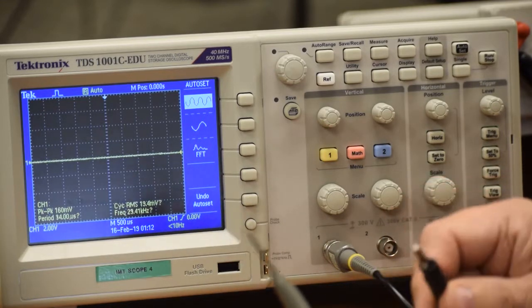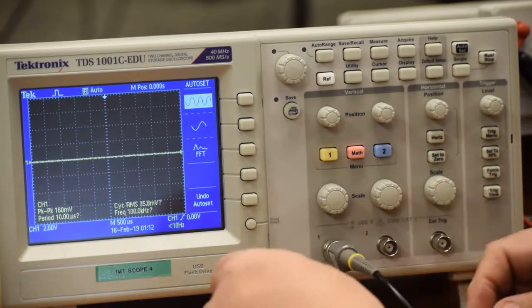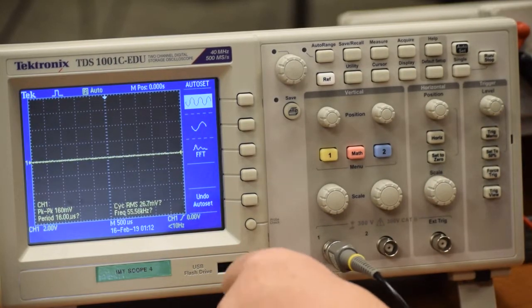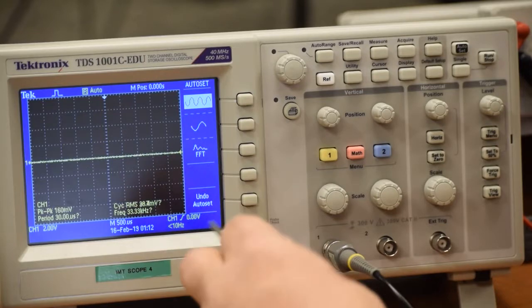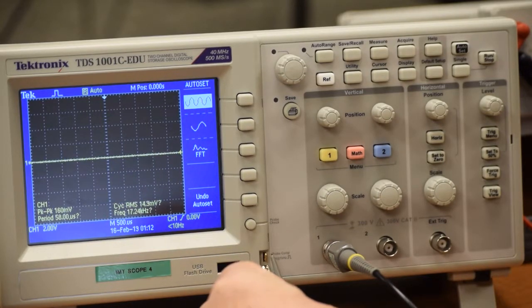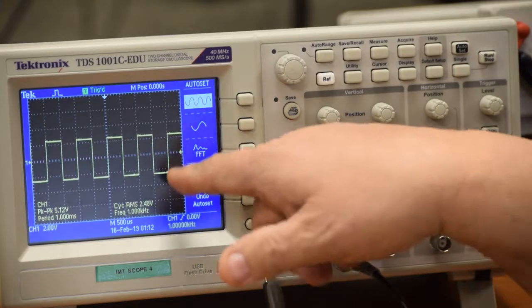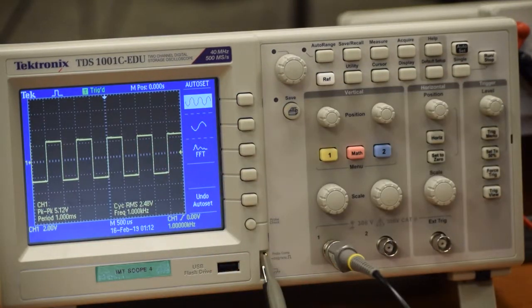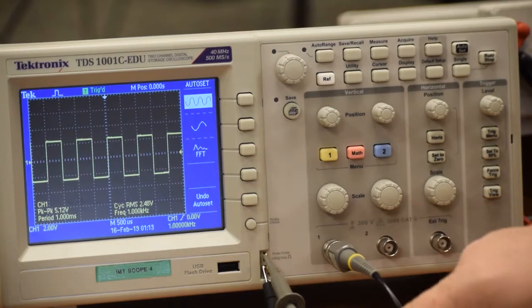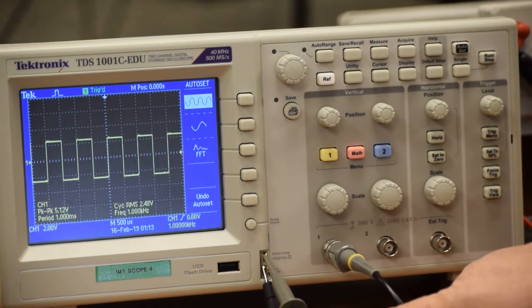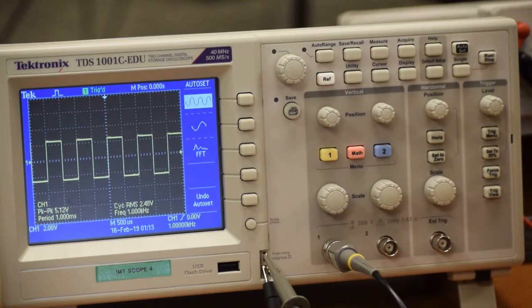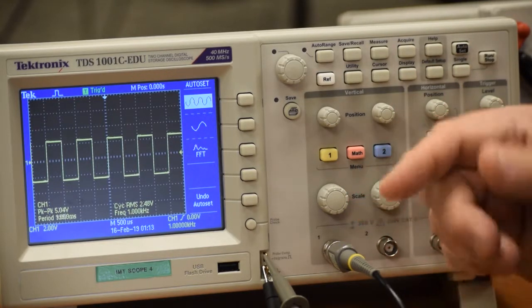And one of the first things you want to do, and you have a capability here where it's already permanently installed as a ground connector, and then you put your OScope on this point right here. Notice we just went to a square wave. And that's how you would make adjustments and calibrating the probe. It's a good idea to do that daily. You want to be on times 10, and I'll talk about that in a moment, but the probe should be on times 10. So with a probe, you can have a times 10 or times 1. And that's not increasing the signal, it's actually attenuating it.